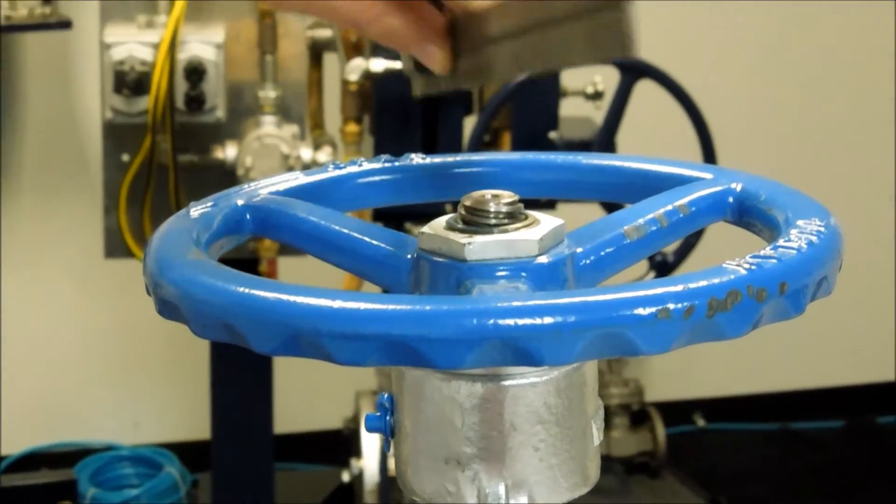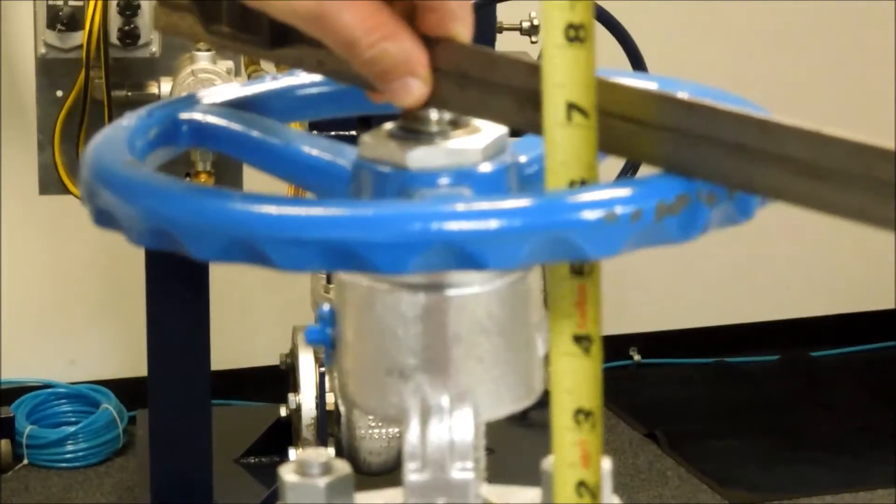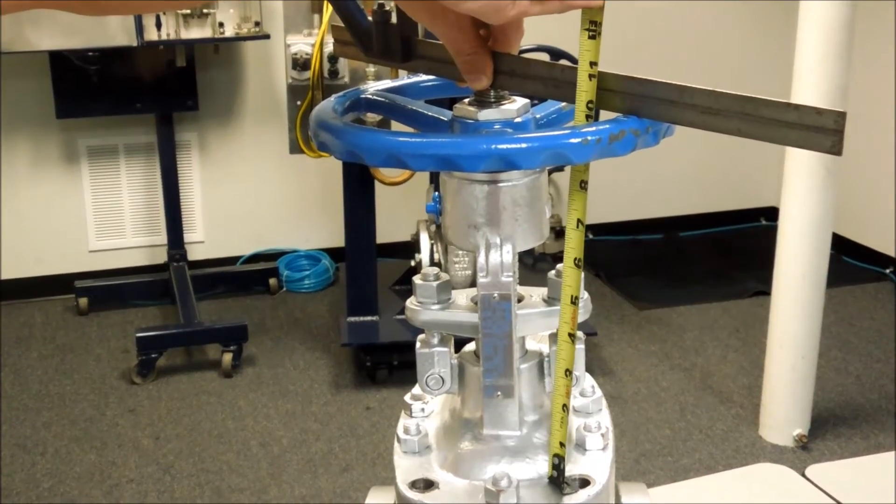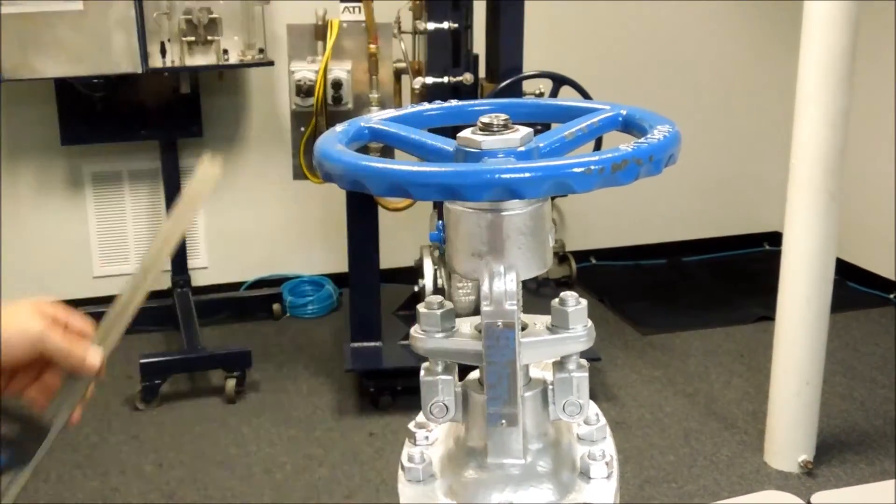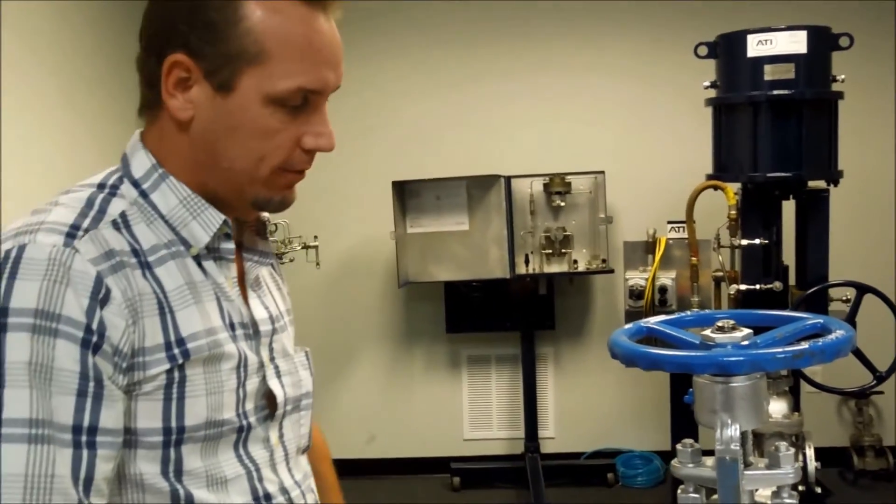Now we are going to obtain the closed stem height using the same process, measuring from one surface to the other. And the difference between the open stem height and the closed stem height is going to be your valve travel.